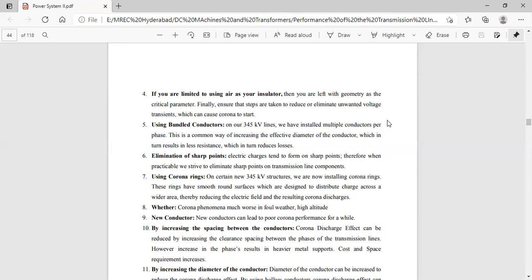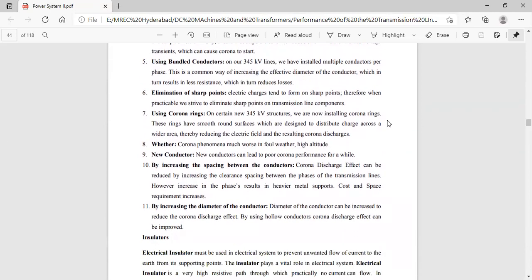Next, this is weather. Corona phenomena are much worse in foul weather and at high altitude. In foul weather, the corona discharge is very heavy, very high. So the weather is also a very important parameter here. Next, a new conductor can lead to poor corona performance for a while. Next, by increasing the spacing between the conductors, the corona discharge effect can be reduced, by increasing the clearance spacing between the phases of the transmission lines. However, increased spacing between the phases results in heavier metal supports, and cost and space requirements increase. This is the drawback of that one.